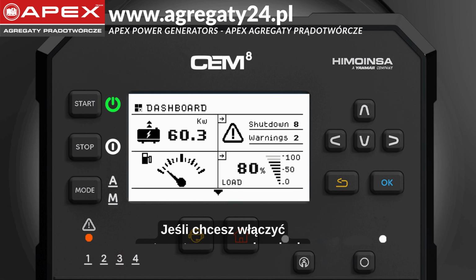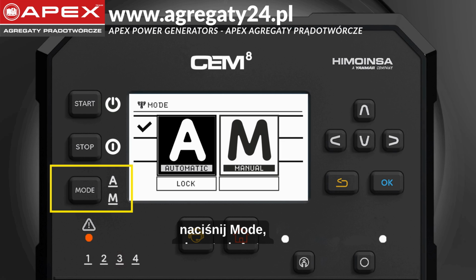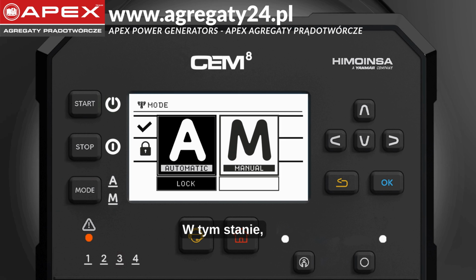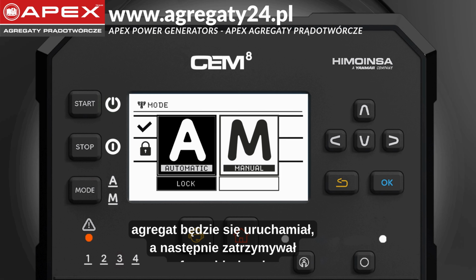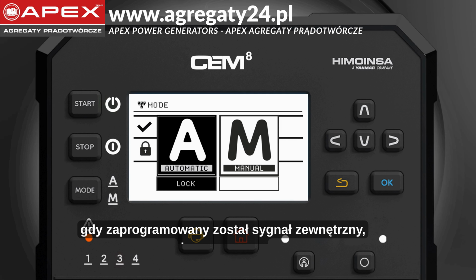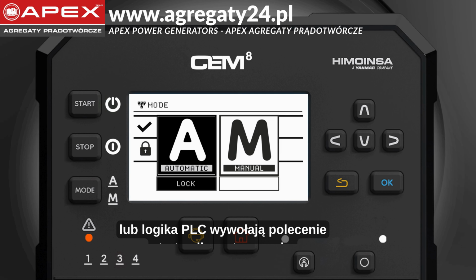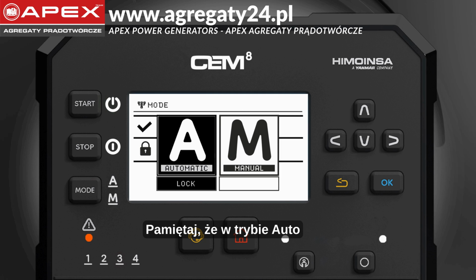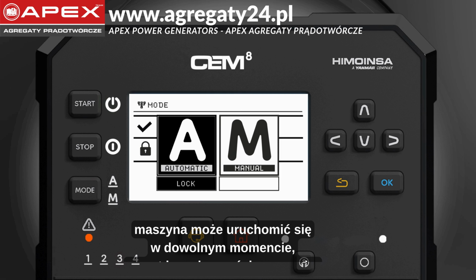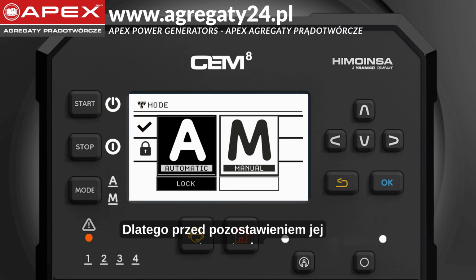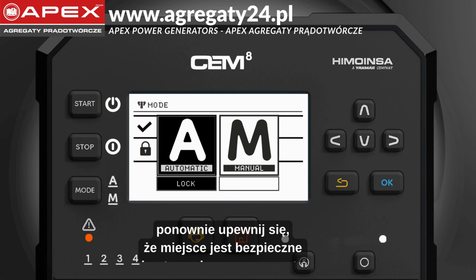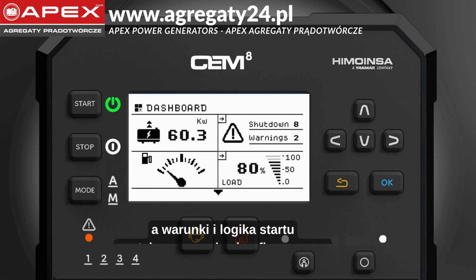Automatic start. If you want to enable automatic starts and stops, press mode, activate auto, and, if needed, lock this mode with lock. In this condition, the generator will start and then stop with cooldown when the programmed external signal, the schedule, or the PLC logic triggers a start or stop command. Remember that, in auto, the machine can start at any time even without personnel present. Before leaving it in this state, verify again that the area is clear and ventilated and that the trigger conditions are correctly configured.